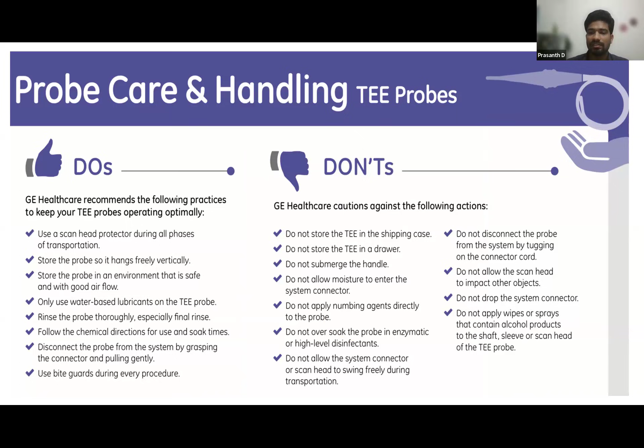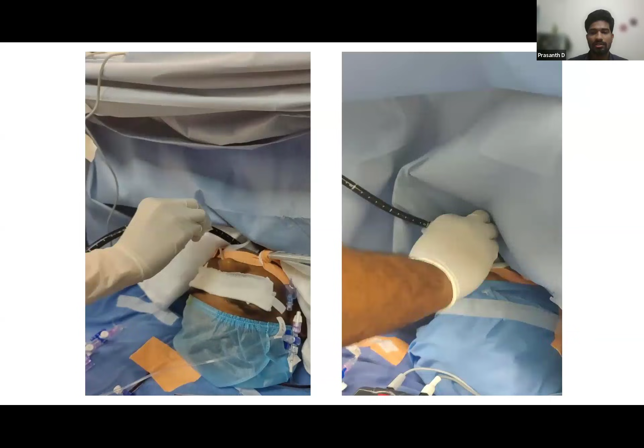Do not store the TEE probe in a drawer or any shipping case, and do not submerge the handle. Only the 100 centimeter shaft and tip should be immersed in the detergents, and do not allow moisture to enter the system connector, and do not over-soak the probe in enzymatic or high-level disinfectants. While removing the probe, it should be removed carefully. After removing the probe, we should remove the mouth bite guard also carefully, without damage to the tip of the TEE probe and to the patient.